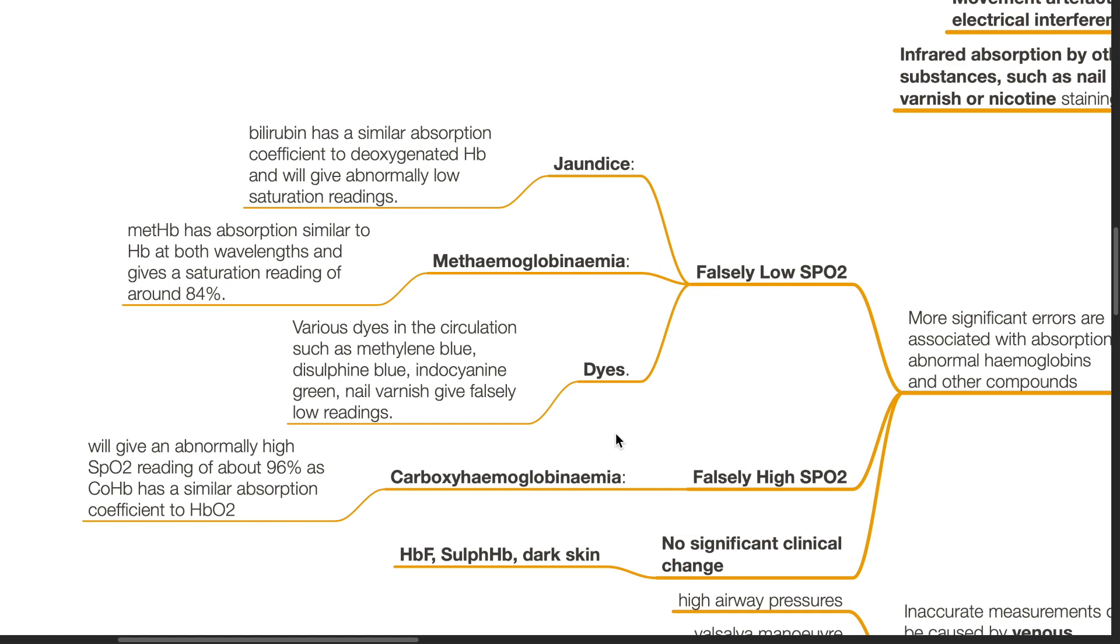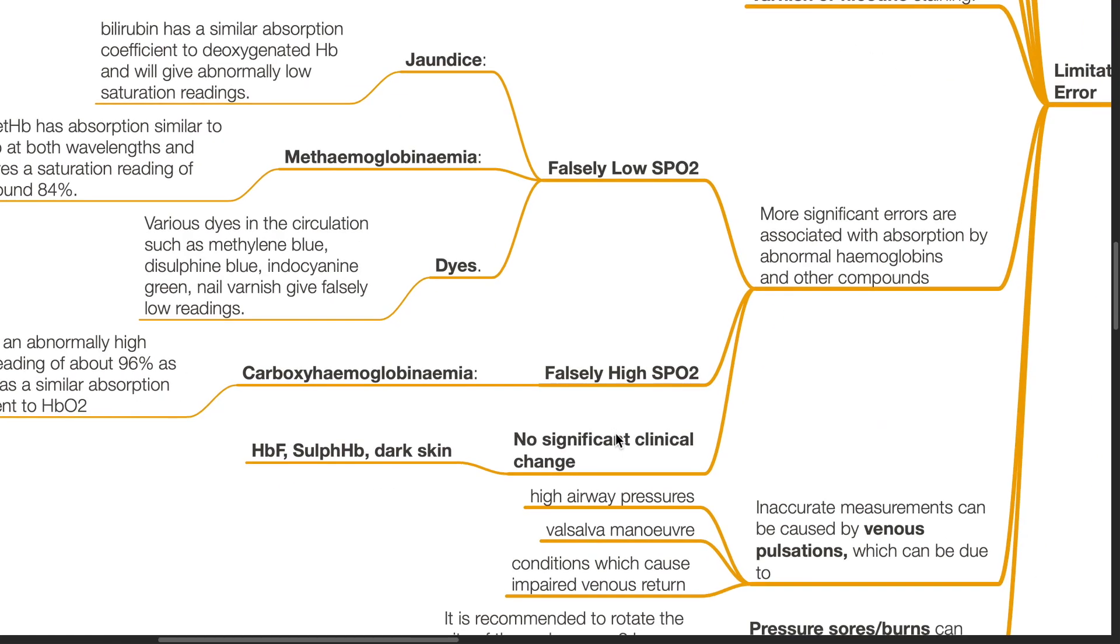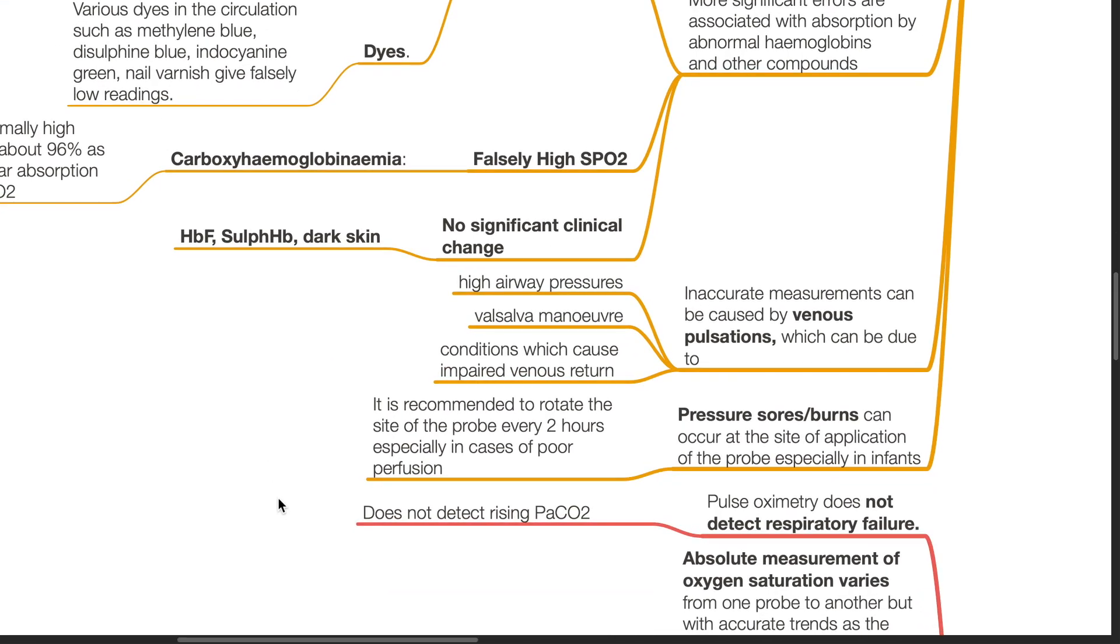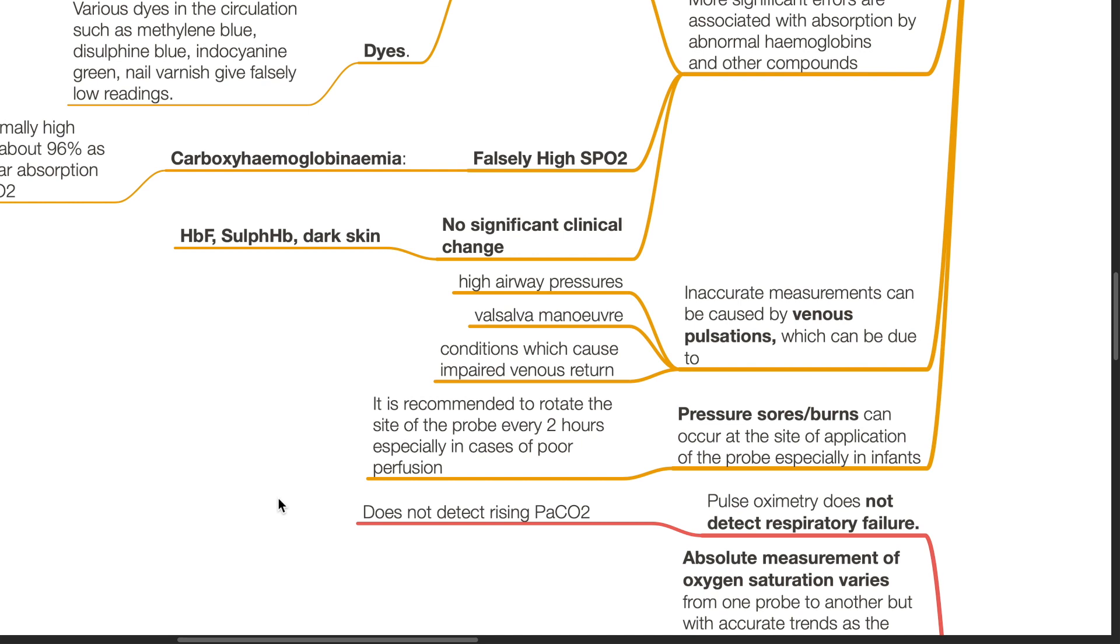There will be no significant clinical change in the presence of HbF, sulfur hemoglobin and dark skin pigmentation. Inaccurate measurements can be caused by venous pulsations which can be due to high airway pressures, the Valsalva maneuver and conditions which impair venous return.